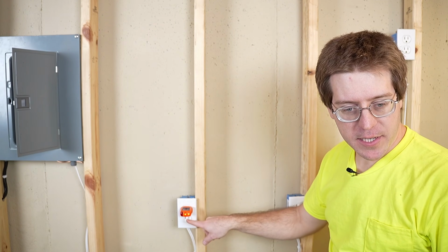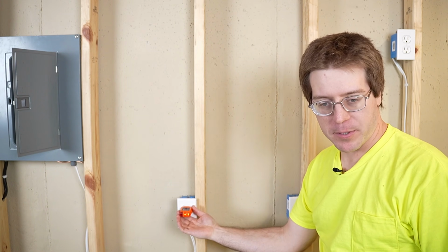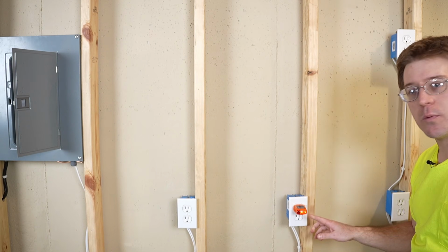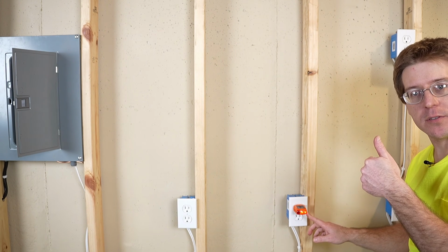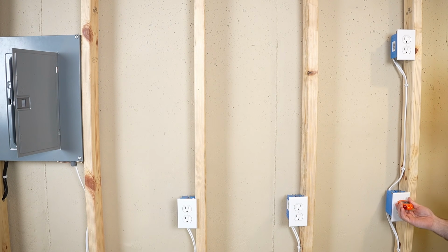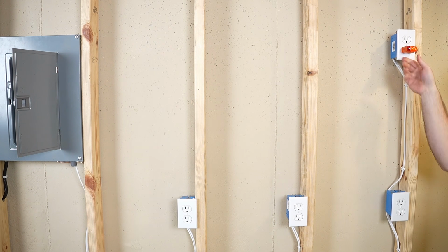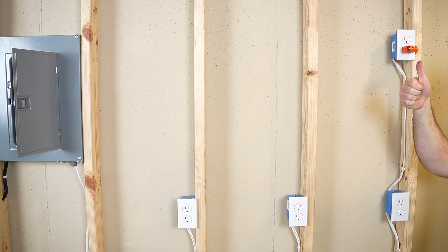Let's check all four of our duplex receptacles. It's as simple as plugging it in. See, we've got two orange lights, that receptacle is good. This one, two orange lights, good. Two orange lights, good. And our last receptacle, two orange lights, that receptacle is good as well.